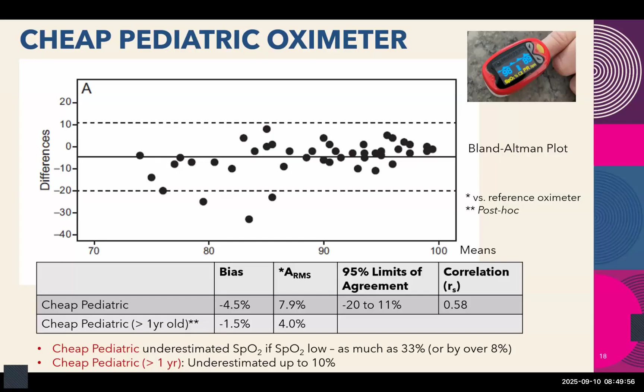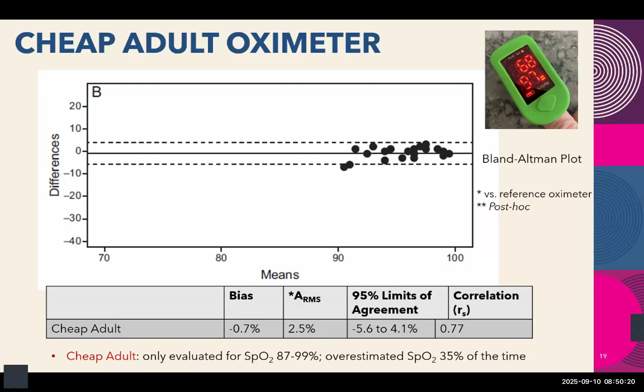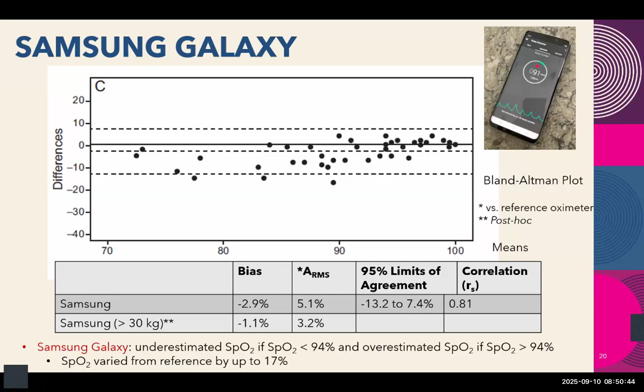For the cheap adult oximeter, it looks really good. Its values are very close to what you expected. The ARMS was 2.5%, but we couldn't find big people with low SATs. So it was a real limitation of our study. We didn't really measure this in the kind of people where you'd really like to know the results. For the Samsung Galaxy, once again, for bigger people with relatively normal SATs, it functioned reasonably well. Though the limits of agreement still varied between about minus 13% and 7%. The ARMS was sort of okay if you were a big person, more than 30 kilos, and it was not adequate if you were less than 30 kilos.